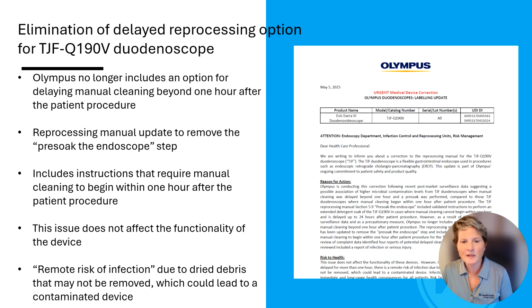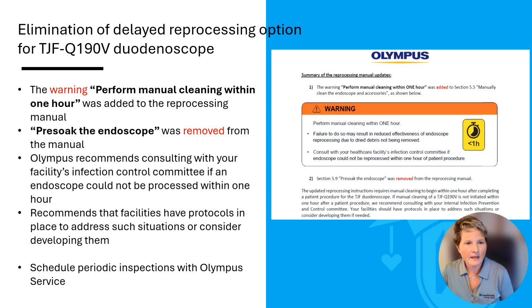So inadequate soaking, or I don't know, I mean, you're allowed to soak up to 10 hours. I'm sure probably a lot of people don't do that. So maybe they're just eliminating that risk. And certainly allowing the facilities to take that on if they choose to do any delayed reprocessing. So the warning here says perform manual cleaning within 1 hour. That was added to the reprocessing manual.